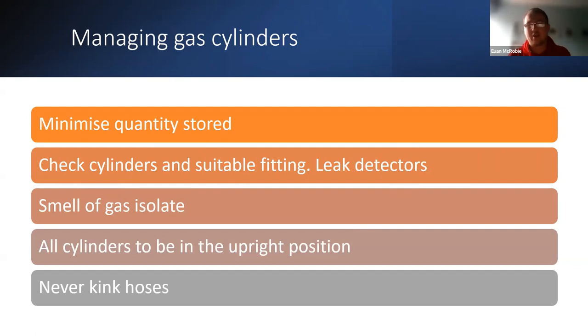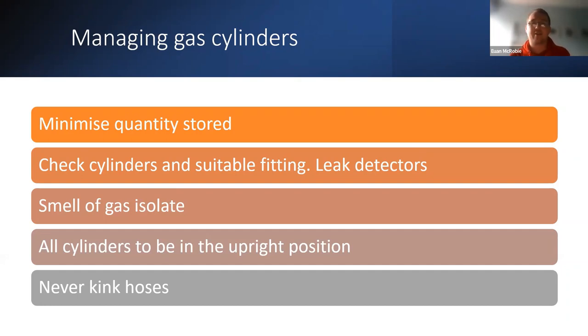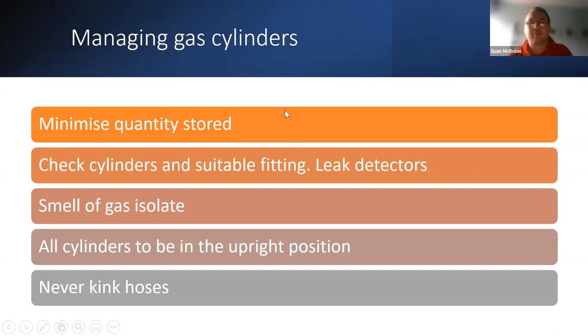Always keep gas cylinders in the correct upright position and never kink hoses. Acetylene has the largest flammable range of any gas — 2 to 92 percent — so it must be used in minimum amounts and in the correct way. When using multiple gases, you may need to compile a DSEAR (Dangerous Substances and Explosive Atmospheres Regulations) risk assessment to mitigate cross-flammability. When stored on site, ensure cylinders are in locked cages at a suitable distance from each other.